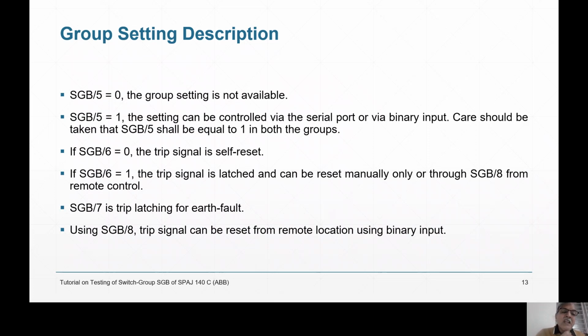But a very important thing is that if in group 1 SGB 5 is equal to 1, then in group 2 also SGB 5 must be equal to 1, because in group 2 also SGB 5 is there. If it is not 1 in group 2, then the relay will be under confusion. SGB 5 equal to 1 in the first group means the relay says you have to go to group 2. But when you go to group 2, group 2 says SGB 5 is 0. So you have come to the wrong place, you have to go back. So the relay will just toss, it will just go here and there. So one has to remember that SGB 5 has to have the same value in both the groups.